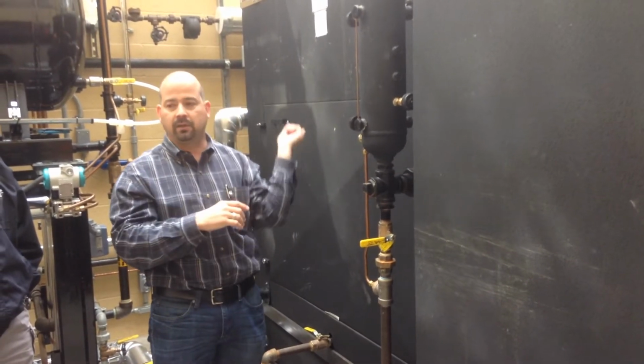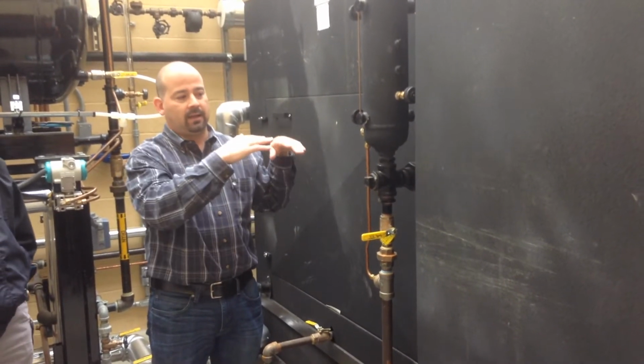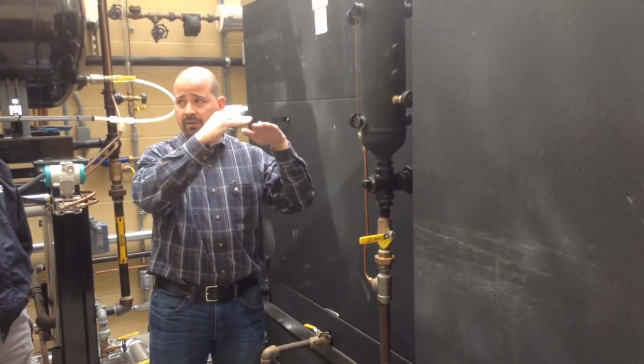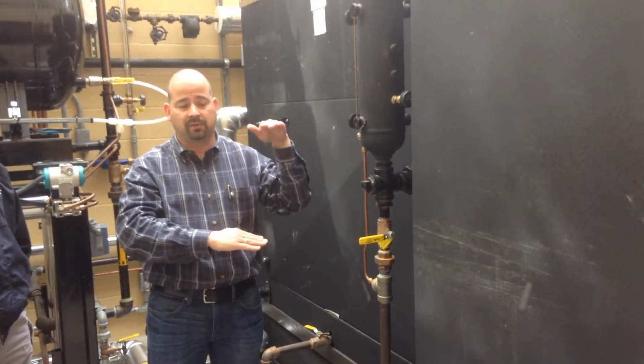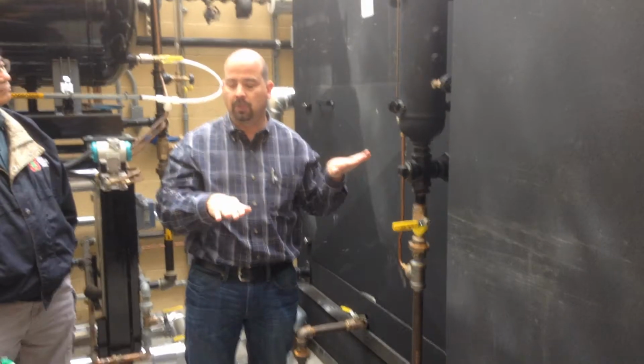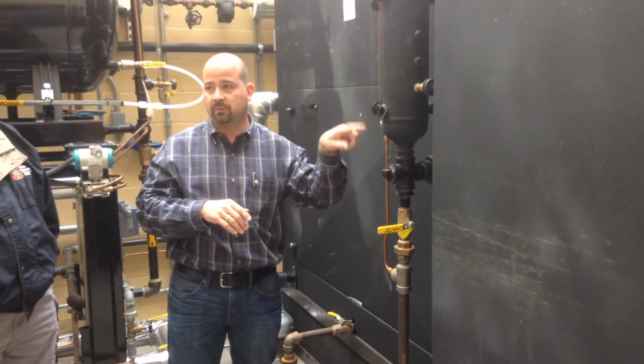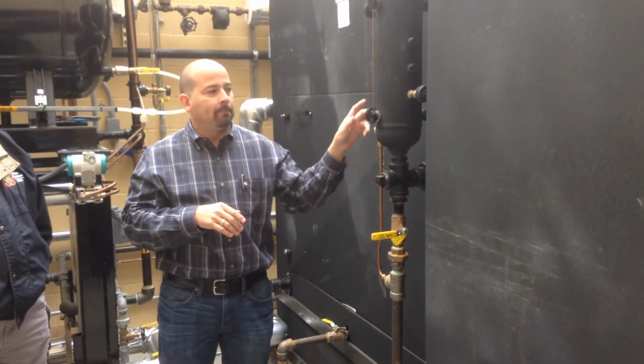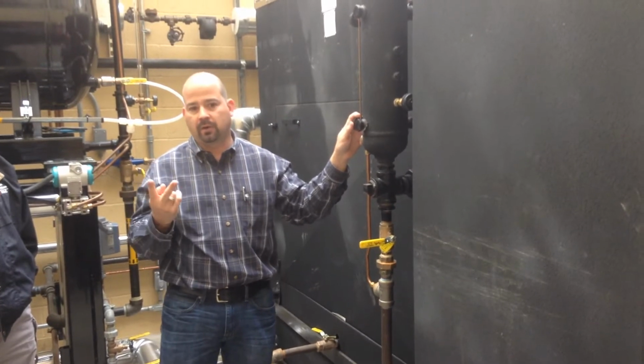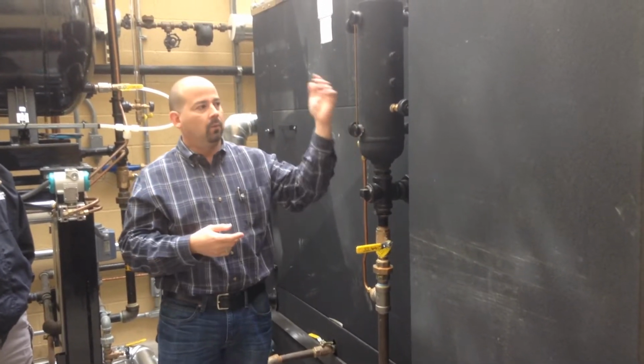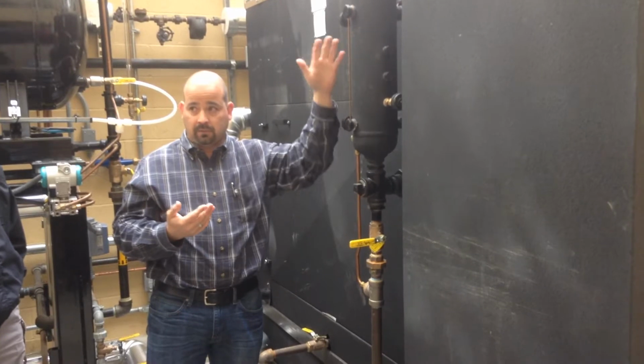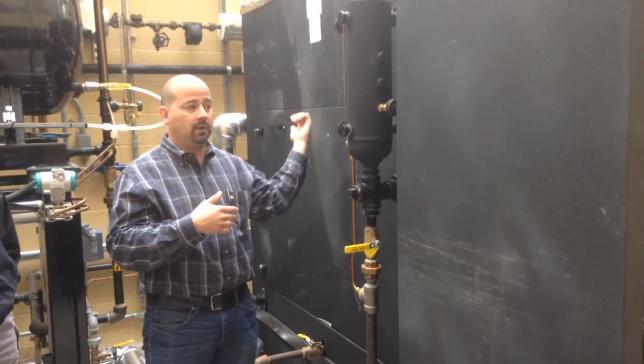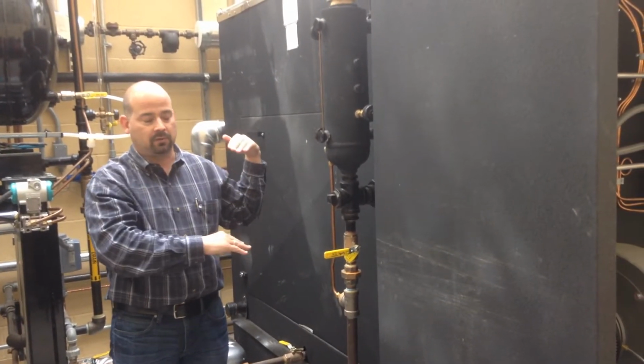So we have a secondary probe in a different location that is a manual reset, so if the water level continues to drop below the lowest permissible, it'll sound an alarm, shut off the boiler, and will not fire unless you manually reset it. We'll go over that in a minute. But it's important to know, there are 2 low water cutoffs per Title 8 Cal Code. One is an automatic reset, which is the one in here. The secondary one in a different location is a manual reset.